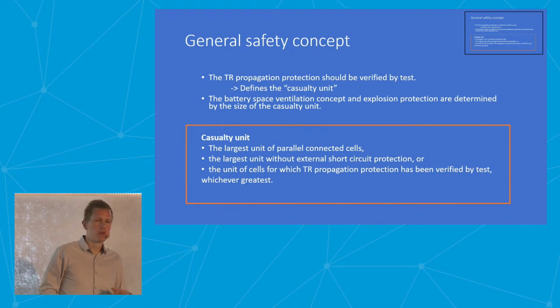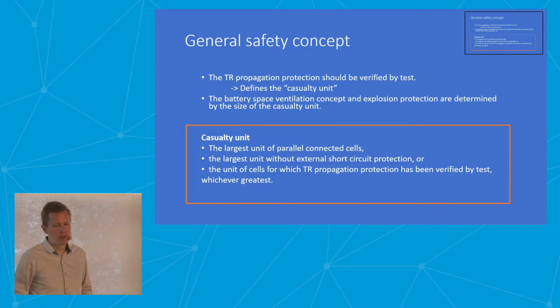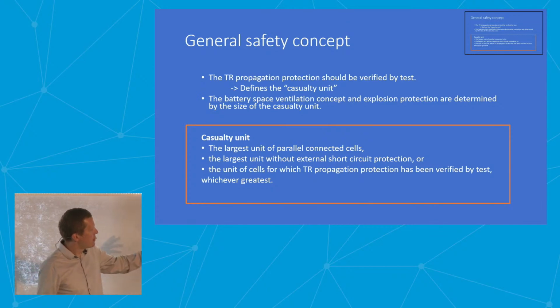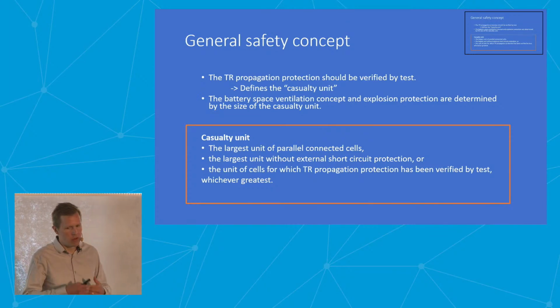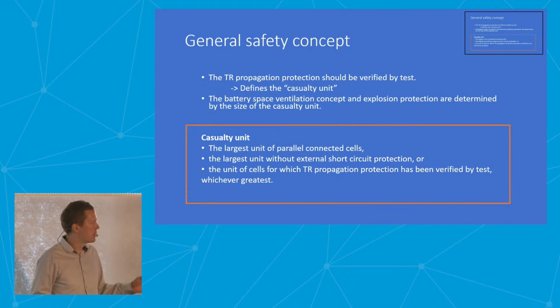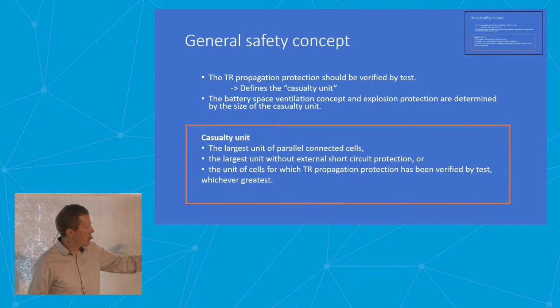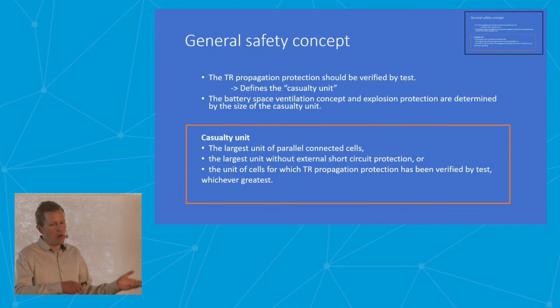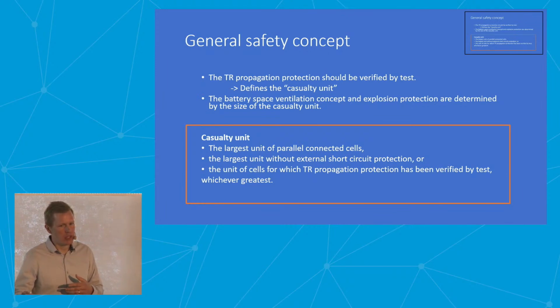We didn't want to talk about battery module, for example, because that's quite vaguely defined, and different manufacturers could mean different things. So we just made this up, called it a casualty unit. What it is, is based on thermal runaway propagation tests, but not only that - it could also be the largest unit of parallel connected cells, or the largest unit without external short circuit protection, or the unit where you tested propagation, whichever is greatest.